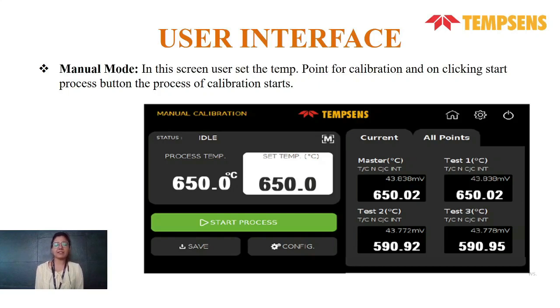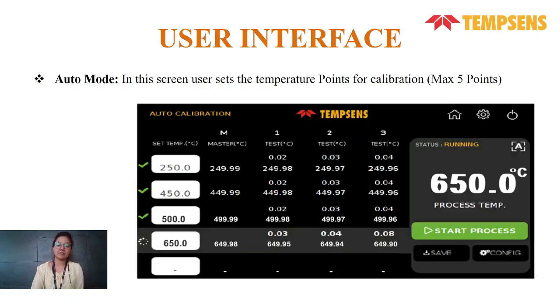As we can see, this is our manual mode window. When we operate manual mode, a window opens on our LCD display. We can easily set our set temperature and touch start process. The process will automatically start. We can see the 4 channels: master, test 1, test 2, and test 3, and the ongoing temperature with the respective millivolts.